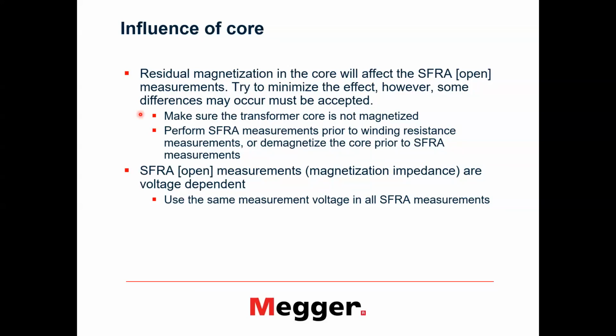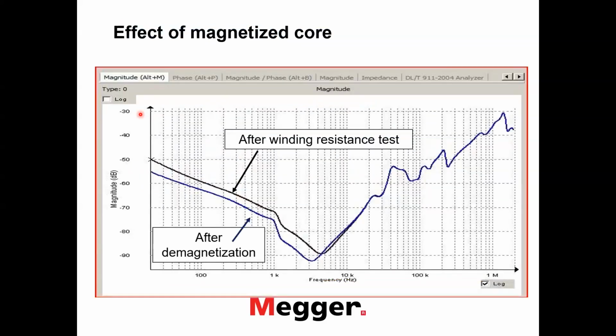And also, besides the magnetization itself in the core, the open circuit measurements are also voltage dependent. I would not say that voltage dependency is of much concern now, when we normally do the measurements at the same and maximum possible voltage. But nevertheless, I will illustrate it. The magnetization effect on SFRA measurement we can observe as changes in the response or changes in attenuation. After a winding resistance test, we can have a higher magnitude or less attenuation due to residual magnetization in the core. And when we demagnetize, we get another picture, another way of looking at the data.